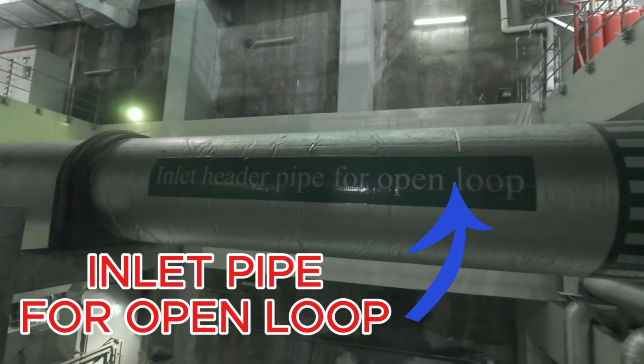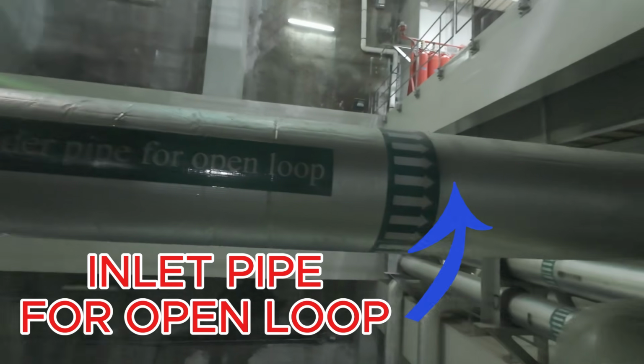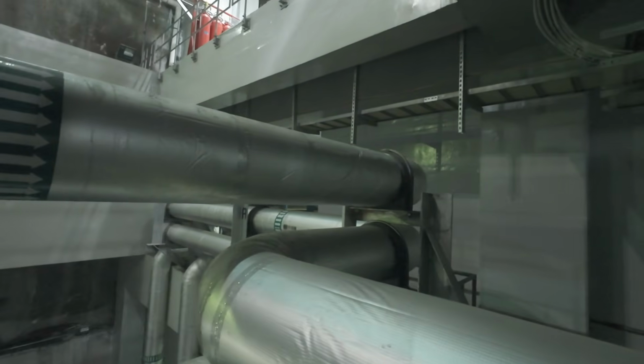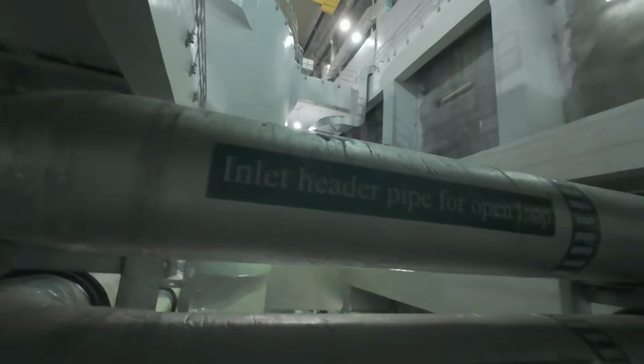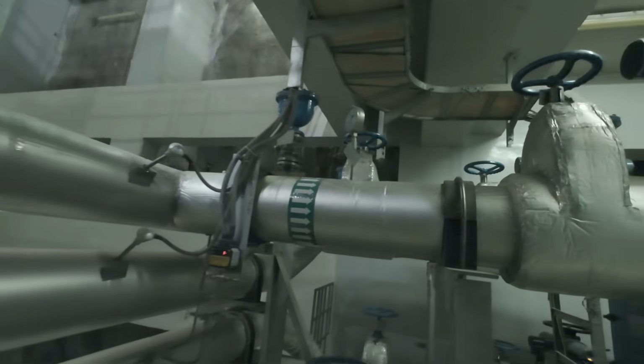Now, the cold raw water finally enters the heat exchanger. At the same time, hot closed loop water arrives from the generator equipment. Heat transfers through the plates, the raw water becomes hot and gets discharged back to the tailrace. But the closed loop water continuously circulates inside the powerhouse, and this is where the real cooling happens.